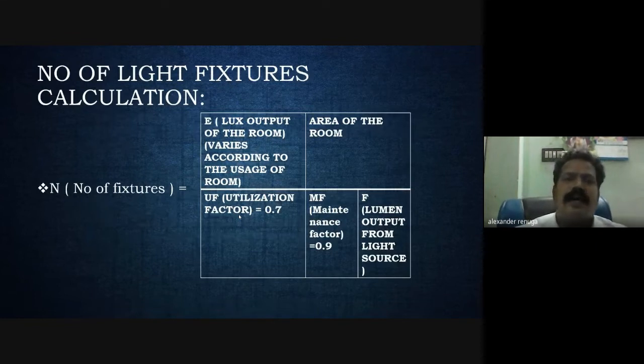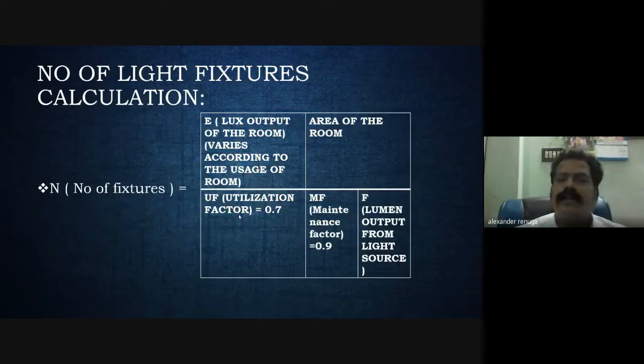For example, a reading room needs more brightness, while a corridor or lawn needs much smaller light. So depending upon requirement and utility, we can change the factors; it may vary from 150 lux to 500 lux depending upon the application. Then area of the room, calculated in square meters. Then utilization factor, generally taken as 0.7, since we consider only 70% utilization.